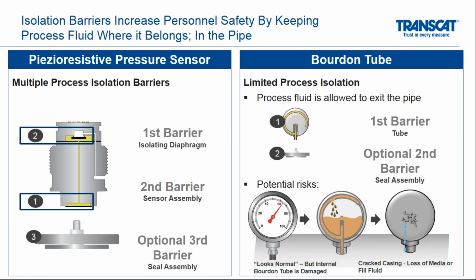So kind of going one by one on some of these challenges, one of them being that fluid could break out. I mentioned these barriers. So as you see there, the first barrier is that isolating diaphragm. But there's a second layer there, or I should say the first layer ultimately is probably the sensor assembly, but there's two layers, and that's a big key here. If you look to the right, you know that all this process is going in that Bourdon tube. You would need to actually add a separate seal assembly in order for it to have two isolating barriers. And the risk there is that if you don't have those two barriers and you do have hazardous or corrosive kind of media, that can leak into the gauge and ultimately leak out of the gauge. You don't see that with a piezo-resistive pressure sensor.